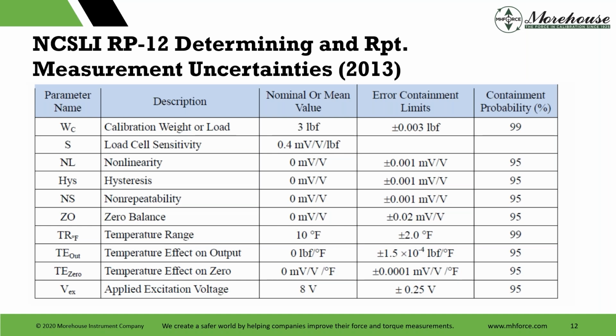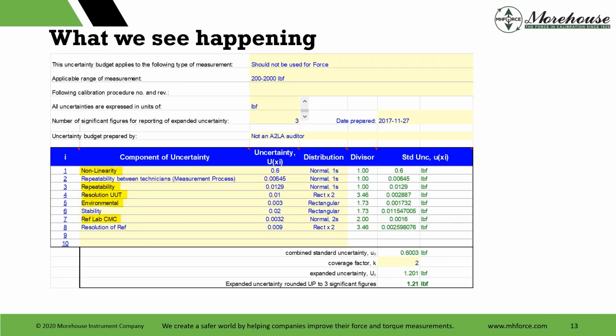and said, move on. The other thing that we see happening when I talked about E74 is someone might use components of uncertainty, and they just say, okay, let's throw them all in, right? And we'll add the reference lab CMC, we'll do all this, and we'll just root sum square them, and we'll say, okay, here, my expanded uncertainty to significant figures is this. But that's only for one part of the range, right? It's only for one single point. If I say at capacity it's 1.21, what about like repeatability down at the low end?